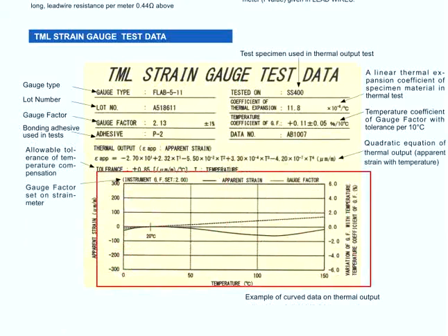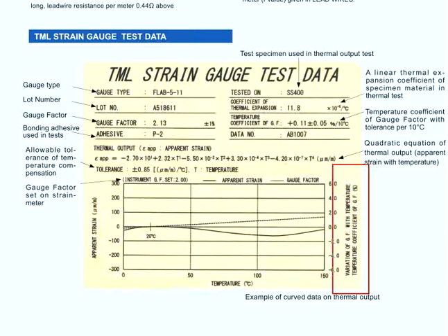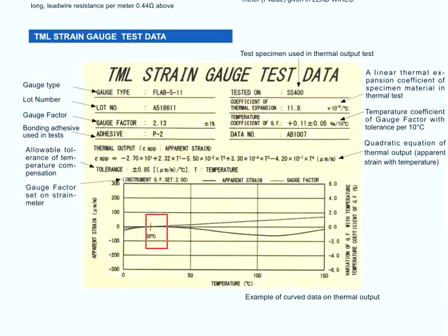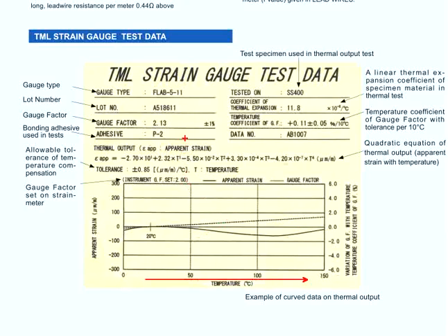There will also be a curve here allowing you to make corrections in terms of the gauge factor when you are using the strain gauge at temperatures other than 20 degrees Celsius. Very little variation will be imposed on the gauge factor if the testing environment temperature is close to 20 degrees Celsius. However, as the temperature increases, the variations in the gauge factor increase, as represented by the dotted line shown here.